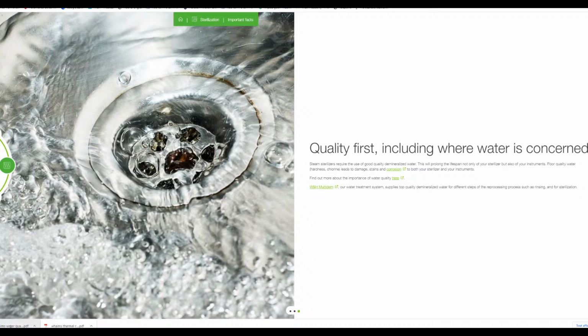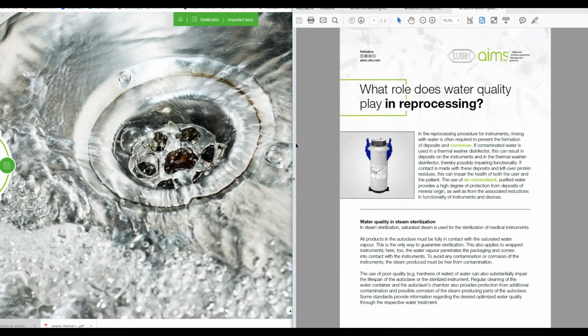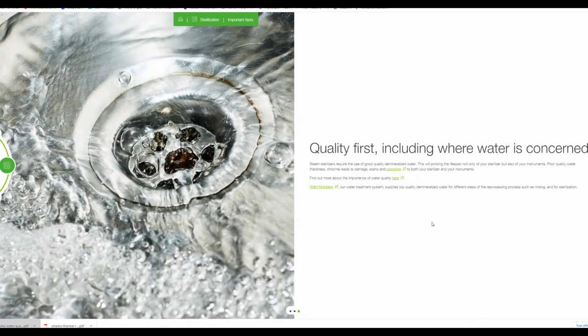We have a PDF here. I'll just quickly open it to show you the role of water. Water is very important. It's quite complex, not only for sterilizers, but also for thermal washer disinfectors. Very often, ideally, you would also connect a demineralizer to your thermal washer for the last rinse, so the last rinse is made with demineralized water. So we avoid any further issues with stains when you sterilize your instruments later on.